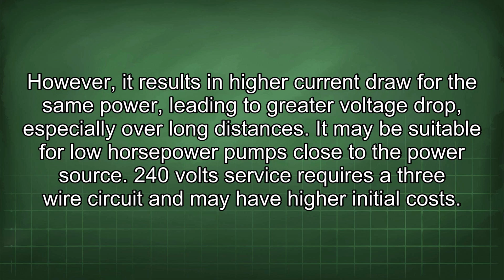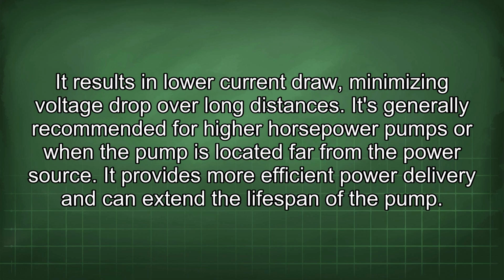240 volt service requires a 3-wire circuit and may have higher initial costs. It results in lower current draw, minimizing voltage drop over long distances. It's generally recommended for higher horsepower pumps or when the pump is located far from the power source. It provides more efficient power delivery and can extend the lifespan of the pump.